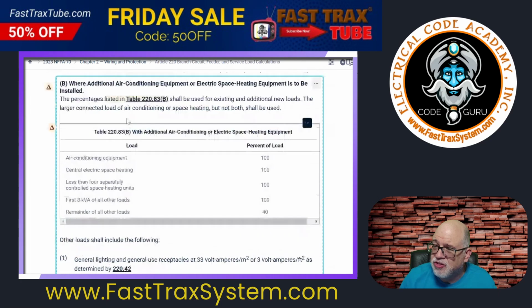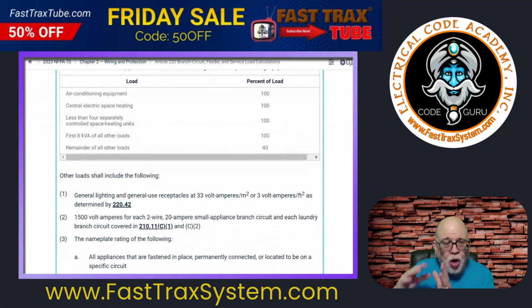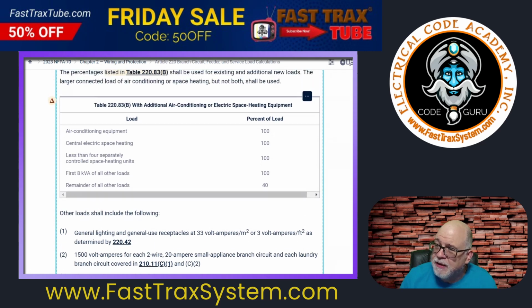The only thing that's changing is that you do all of that calculation just like we just did. But now if you have additional air conditioning equipment, you take it at 100%, or you have central electric space heating, you take it at 100%. Or if you have less than 4 separately controlled space heating units, you take them at 100%.